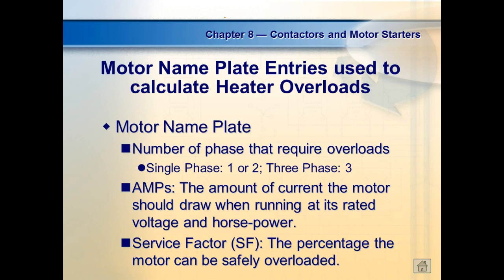Then a lot of motors will have what we call a service factor. The smallest service factor you'll ever have is one, but it could go up. I've seen 1.25 service factor. This is the percentage by which we can safely overload the motor. Are we okay? Well, those are the three things we're going to look at: the number of phases, the amps, and the service factor. These things are going to determine what size heater overload we're going to get.